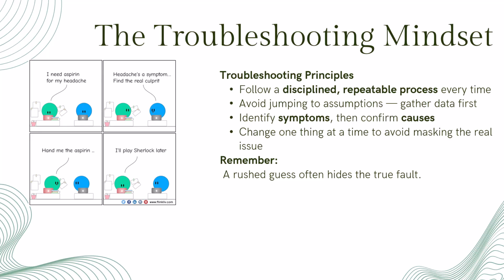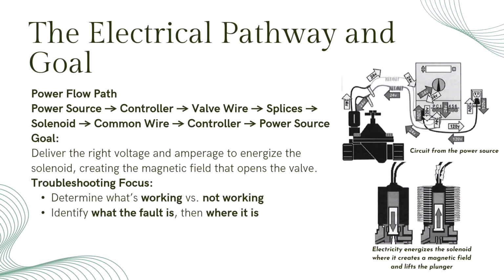Effective troubleshooting isn't guesswork, it's a process. Even experienced technicians can fall into the trap of jumping to conclusions. But when you assume the cause, you risk missing related problems or covering up the real issue. Develop a step-by-step process that works for you and follow it the same way every time. That consistency is what separates an efficient technician from one who wastes time chasing false leads.